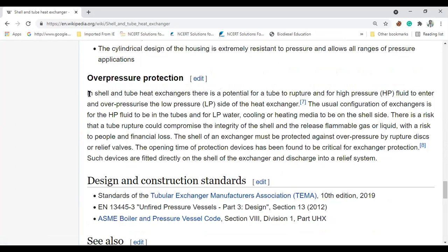There is a design consideration for overpressure protection: in a shell and tube heat exchanger, there is a potential for a tube to rupture and high-pressure fluid to enter and over-pressurize the low-pressure side. The usual configuration is for the high-pressure fluid to be in the tubes. Always keep high-pressure fluid in the tubes and low-pressure fluid in the shell side.